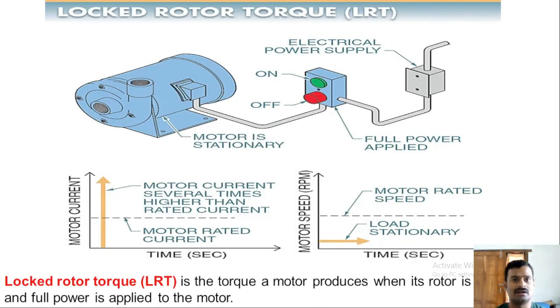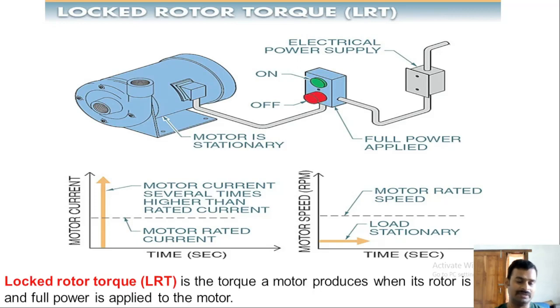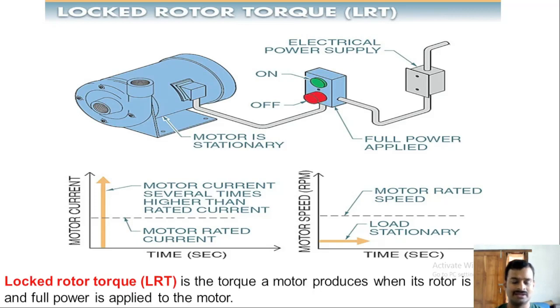Locked rotor torque (LRT) is the torque a motor produces when its rotor is stationary and full power is applied. When the motor is in standstill condition and we give full rated power, the motor starts rotating. The torque produced at that moment is called locked rotor torque, and the current taken to produce this torque is called locked rotor current.